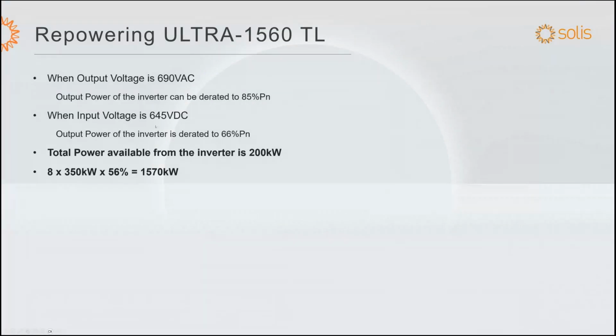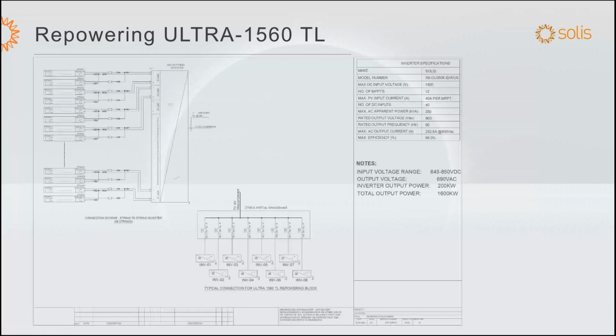And then using the 645 volt DC rating of the Ultra, the lowest rating of the Ultra inverter, the inverter will be derated to 66% of P nominal. So the available power of the inverter is about 200 kilowatt. So that will basically directly repower the Ultra inverter, which is rated 1560. We can generate 1570 kilowatt with this configuration. This inverter again has 12 MPPT, so we can connect 48 parallel strings, up to 4 strings per MPPT, and then have a 690 volt switchgear with a 690 volt breaker going to the medium voltage transformer connection.